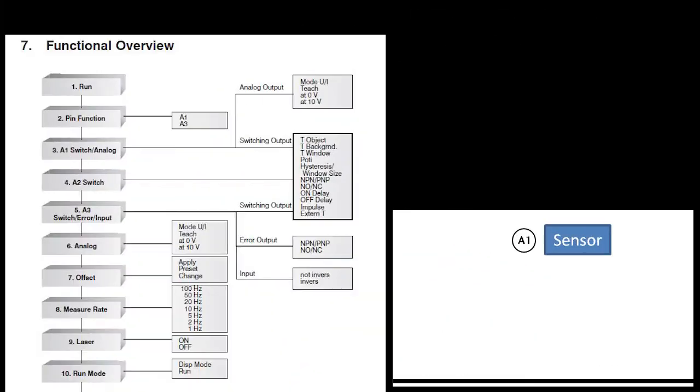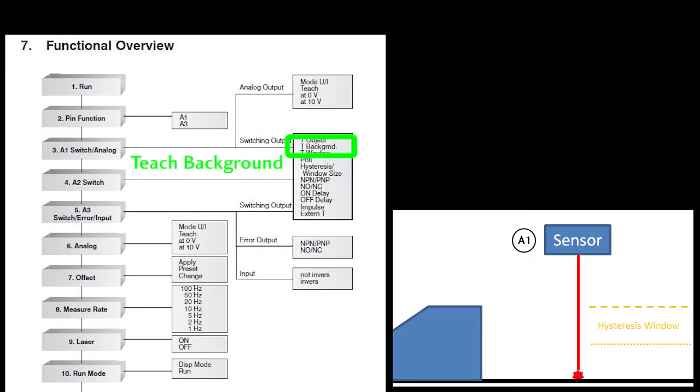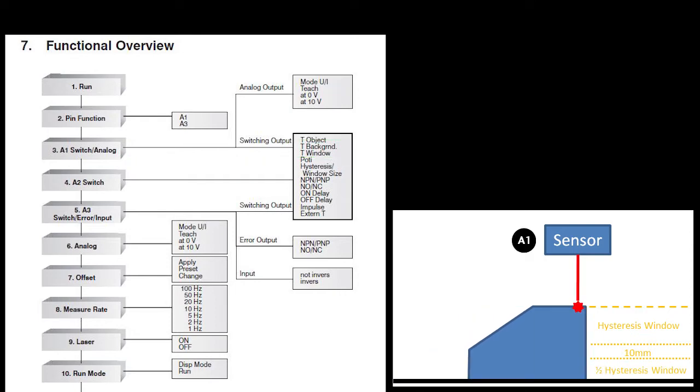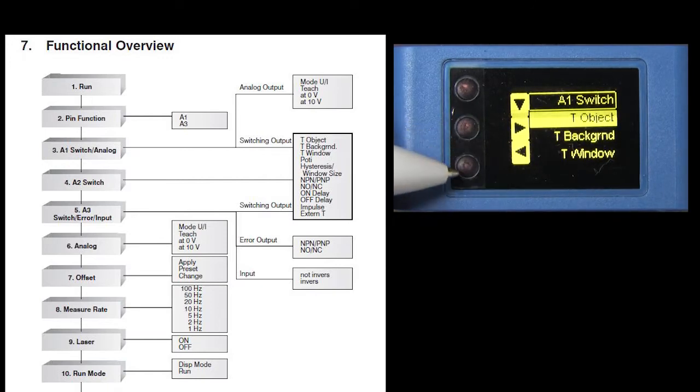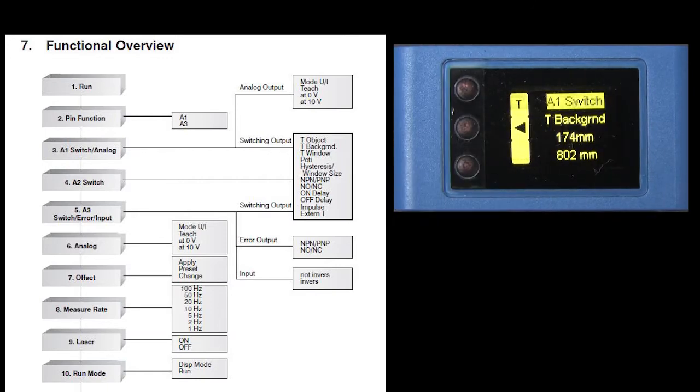This T background menu is very similar except you learn the background and anything that is larger than a hysteresis plus 10mm plus another half hysteresis will be detected and the signal won't be released until it has fallen back below the hysteresis level. To set that up, you just enter the menu item, make sure there are no objects in front of the line of sight and hit T. The sensor calibrates and you are ready to go.